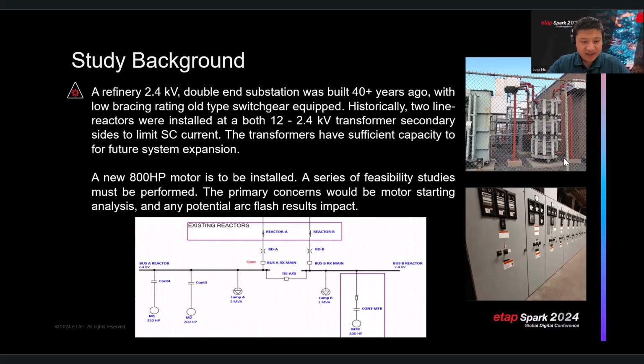The transformers and the substation buses has enough capacity for future expansion. So now the client wants to add an 800 horsepower motor to the substation. A series of feasibility studies must be performed before they do the addition. The primary concern for this addition would be the motor starting analysis and any potential arc flash impact comes with the system change. So here we can see the system has bus A and bus B. They have a tiebreaker to tie the bus, and there are two line reactors, A and B, connected.